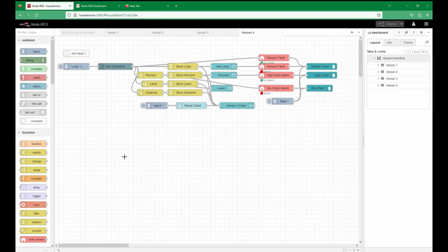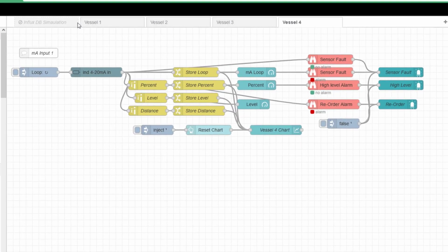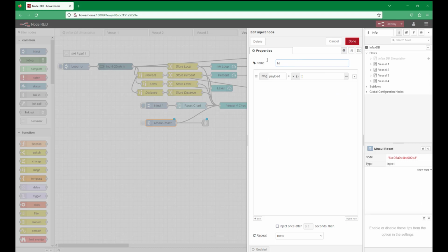So you can see here now I've done an update, and I really can't get my trends to appear. Yeah, so the issue is that each one of my trends here now is full up with 4 data points that have been recording every second for the past hour, and it's pushing the old data out and in, and so they're all full up with all of this data, and it's really slowing the dashboard tool down.